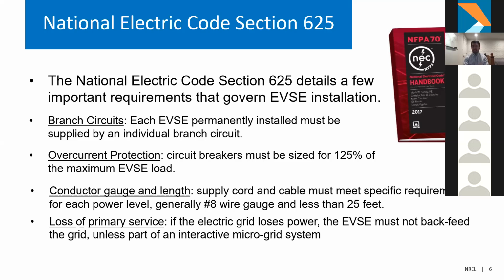And then in terms of that circuit breaker, or what's referred to as overcurrent protection, they must be sized for 125% of the maximum EVSE load. And this is strictly just the overcurrent protection.